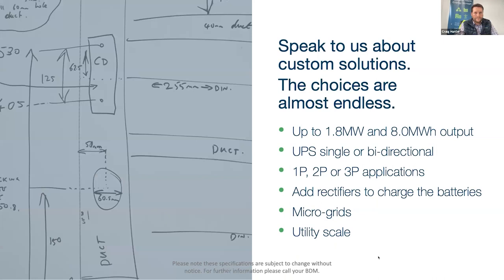As I said, we can take this product to about 1.8 megawatts in output size, 8 megawatt hours of storage. We can do true bi-directional or single directional UPS modules in this product if you want a true UPS style product. One phase, two phase, or three phase applications. We can add rectifiers, whatever you need to do. And one of the big benefits is we can create microgrids with this product as well, with lots of nodes hanging off of it. And it suits the utility scale.